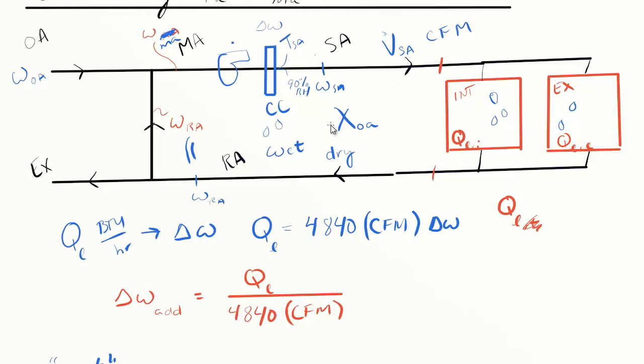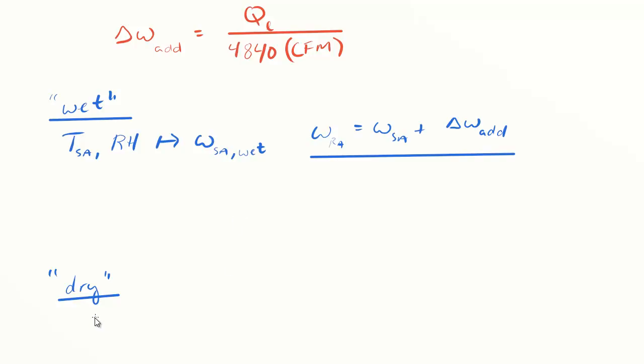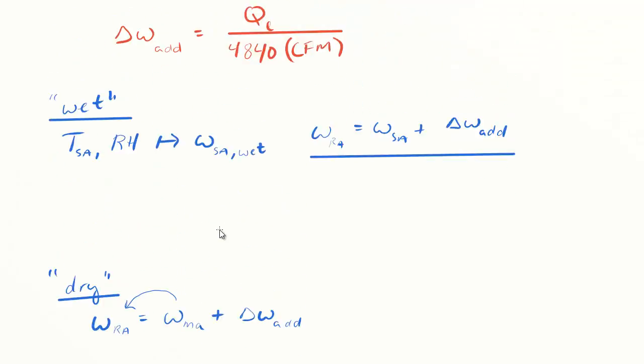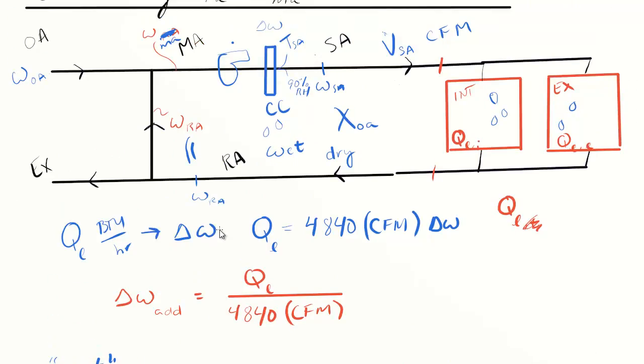That's our first assumption. Now we can do a similar thing. We're going to solve for omega_RA. In this case, omega_RA equals mixed air plus delta omega added. Here's where the confusing part lies - we don't have a specified value. In the wet case, we knew the supply humidity ratio, but here, the mixed air humidity ratio depends on the return air value. We can't directly solve for this.